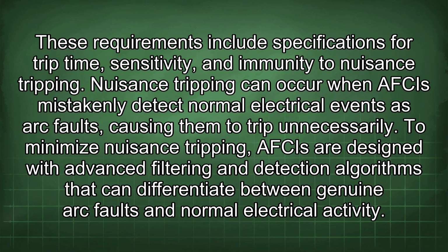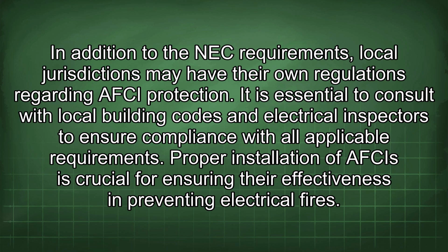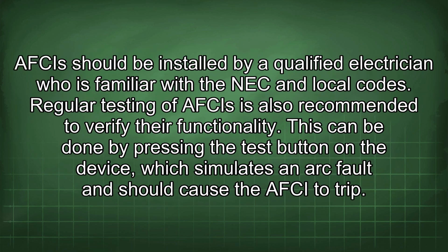and normal electrical activity. In addition to the NEC requirements, local jurisdictions may have their own regulations regarding AFCI protection. It is essential to consult with local building codes and electrical inspectors to ensure compliance with all applicable requirements. Proper installation of AFCIs is crucial for ensuring their effectiveness in preventing electrical fires. AFCIs should be installed by a qualified electrician who is familiar with the NEC and local codes. Regular testing of AFCIs is also recommended to verify their functionality. This can be done by pressing the test button on the device, which simulates an arc fault and should cause the AFCI to trip.